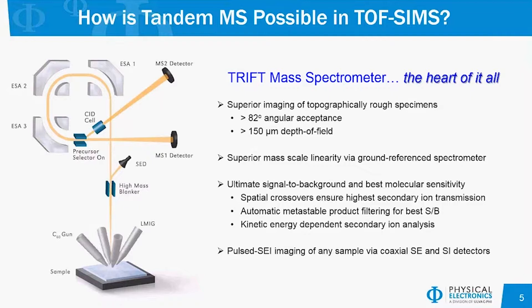Lastly, with the TRIFT mass spectrometer, because the secondary electron detector is part of the mass spectrometer, we have a secondary electron detector as well as the secondary ion detector together. Because those are collinear, we can collect pulsed secondary electron images, which is quite an advantage on an insulating sample.